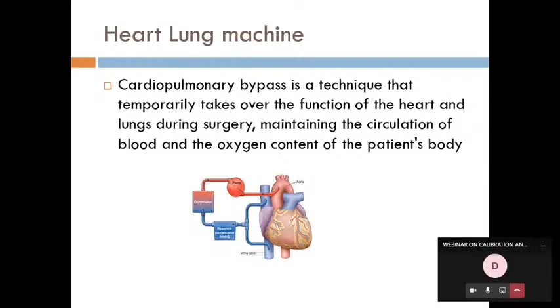Okay, the same thing during the bypass surgery: the deoxygenated blood from the heart is taken to a pump. This pump takes it to a reservoir, and the reservoir will collect all the blood, and from the reservoir it goes to the oxygenator. This oxygenator is nothing but a filter. This oxygenator is connected to air through a blender. This blender will mix the air and oxygen in the correct ratio. From the oxygenator, the blood gets oxygenated. From the oxygenator, the blood goes to a peristaltic pump. From the peristaltic roller pump, once the pump rotates, the blood is pushed into the heart, that is the aorta. From the aorta, it goes to all parts of the body.